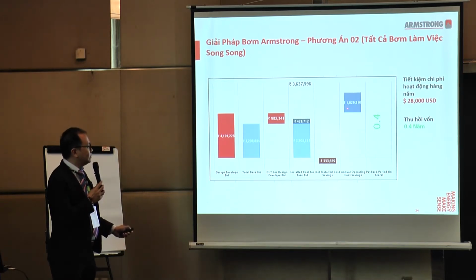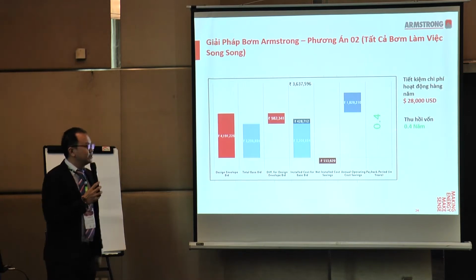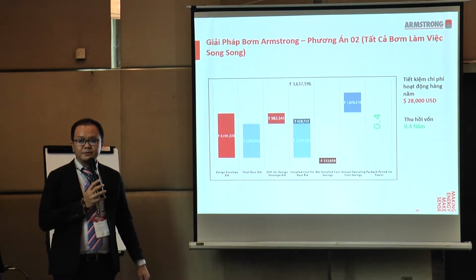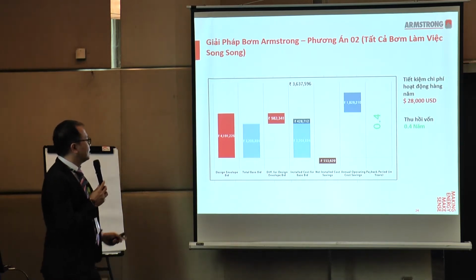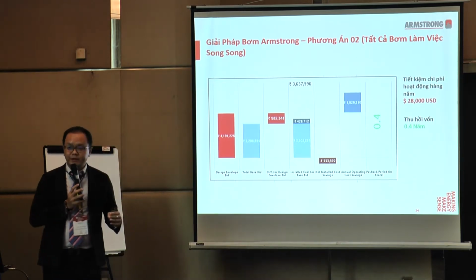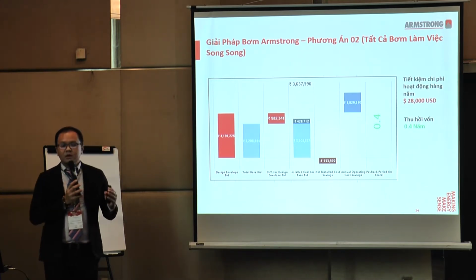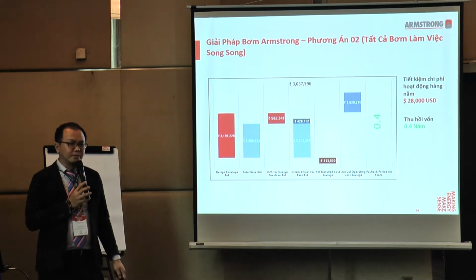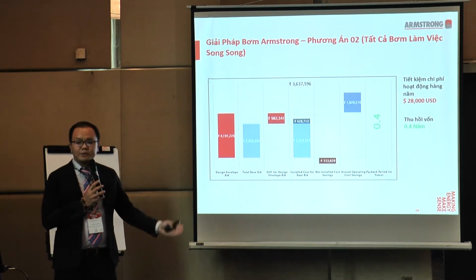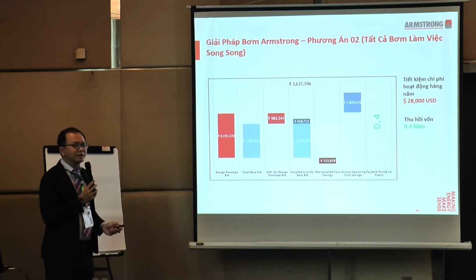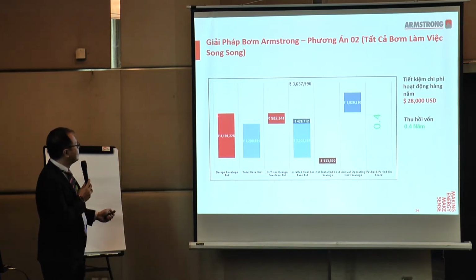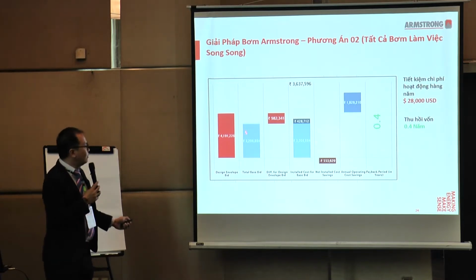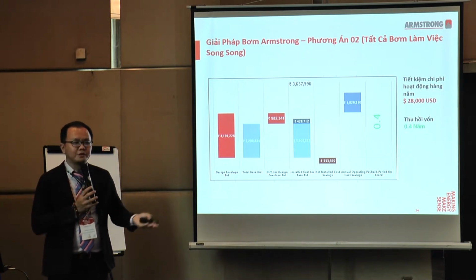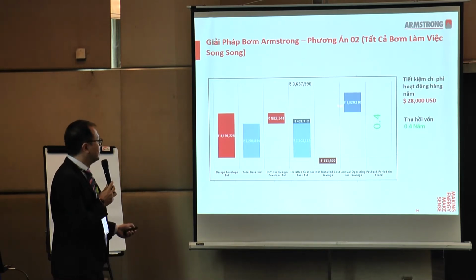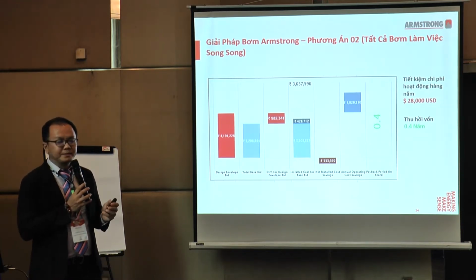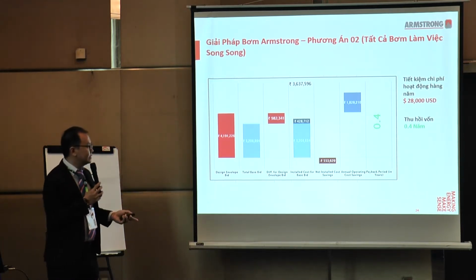So when you actually break this down with this figure, you end up saving it in less than a year. So whether you're looking at running the two different operations, duty standby versus running in parallel, or you're looking at reducing the size of the pump, what matters is really the overall lifespan of your operation, because that is where the saving comes. People are always confused that it's always high on the front side, but over a lifespan of 10 years or so, before you have a change of your pumps or control system, you will actually be able to benefit immediately, as you can see in the first case study and this second case study.